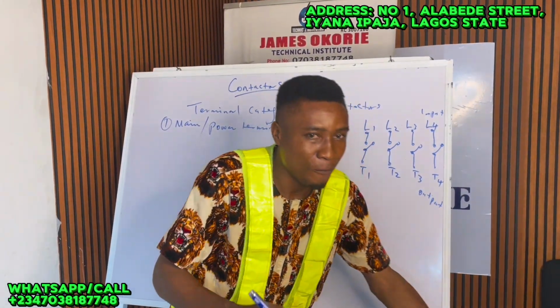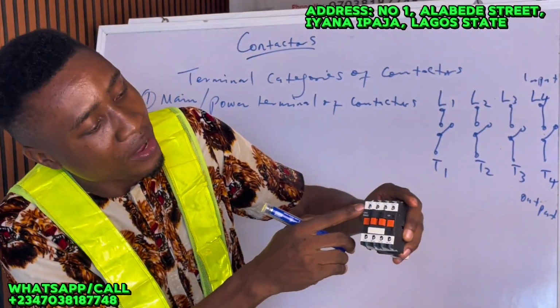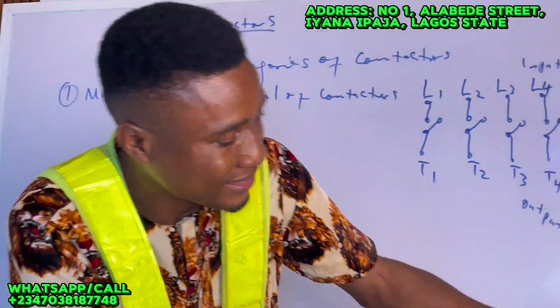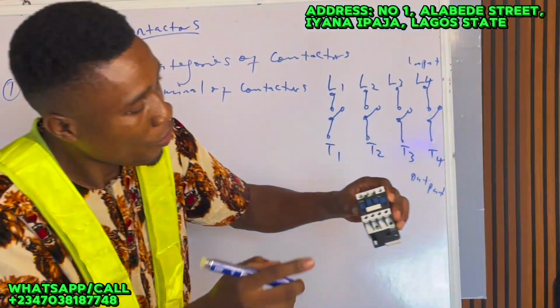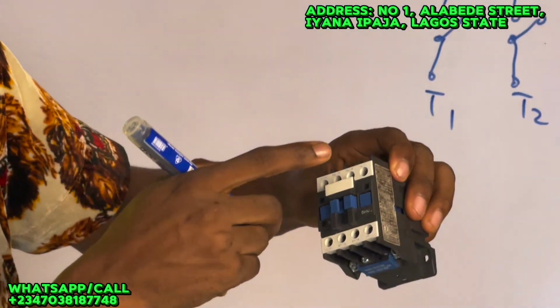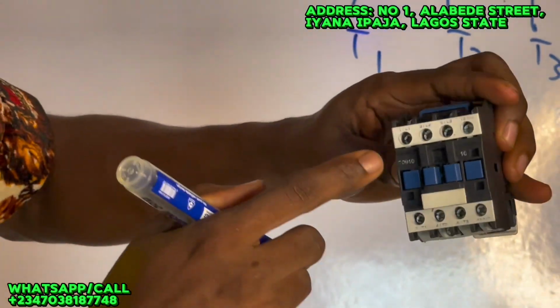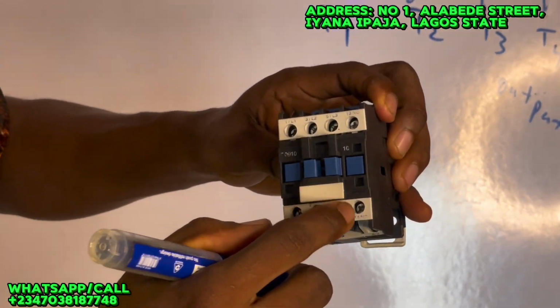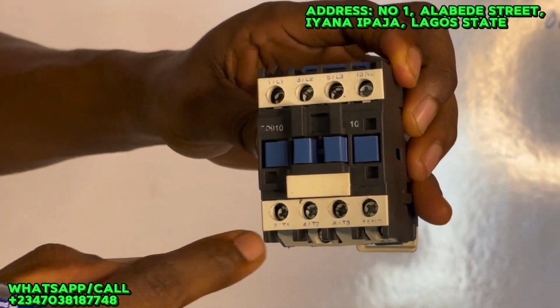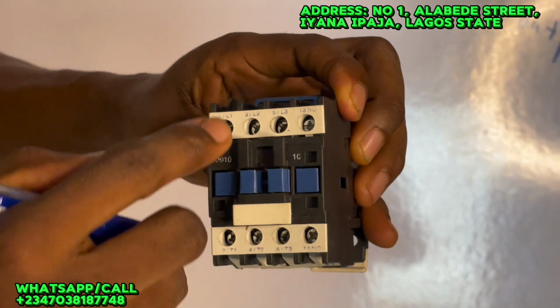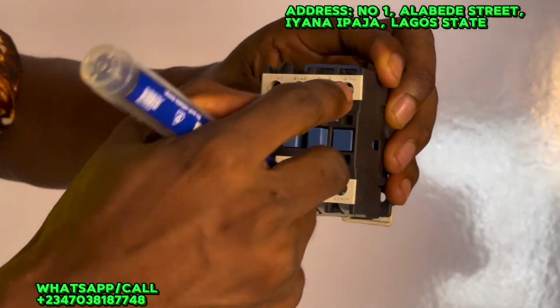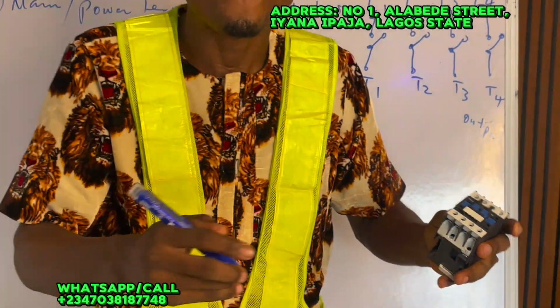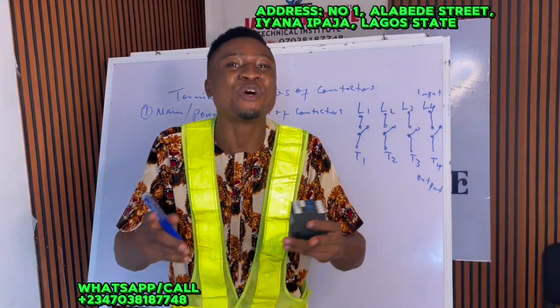When you check this contactor, come closer. The terminals which are the power terminals are here. These are the power terminals, what you call L1, L2, L3, T1, T2, T3. T1 is the output of L1, T2 is the output of L2, T3 is the output of L3. Now there are other terminal categories of contactors, which include the control terminals and the auxiliary terminals.